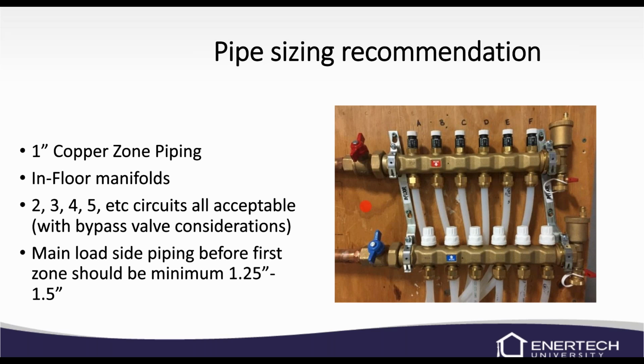We do recommend that the main piping on your load before the first zone is coming in at about 1.25 to 1.5 inches. And then, after your first zone, you can cut that down to 1-inch copper zone piping, but that's totally up to you.